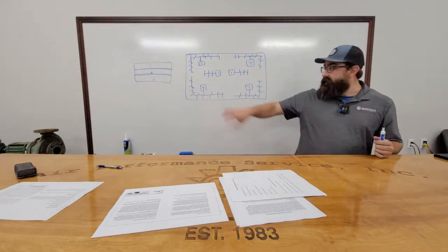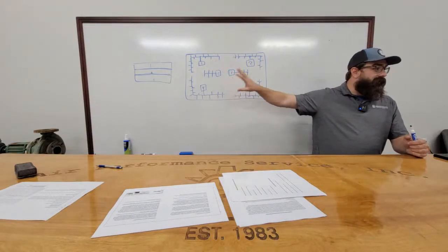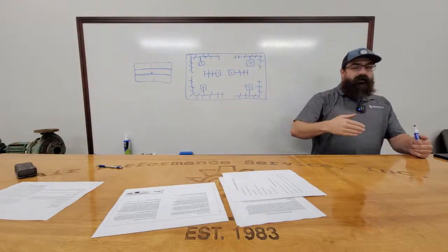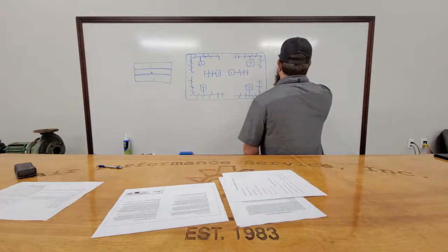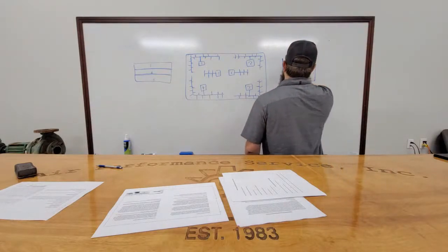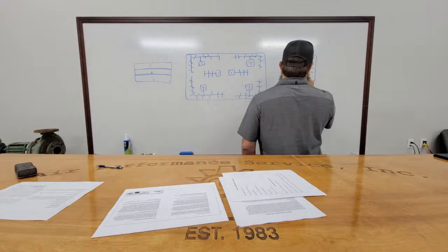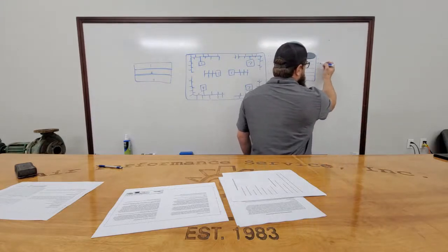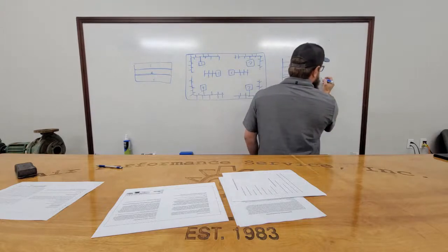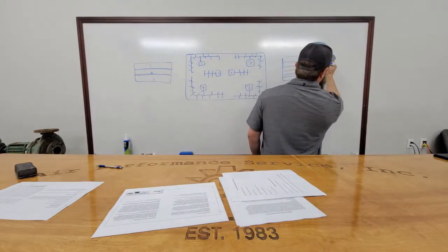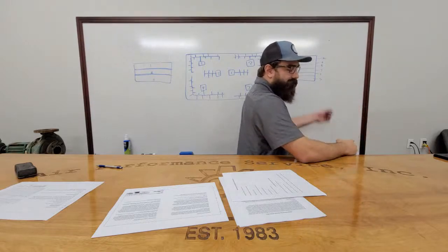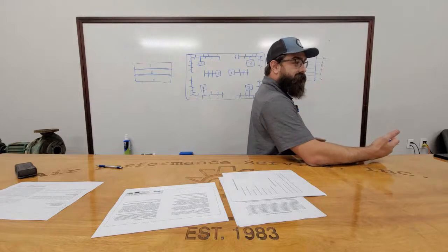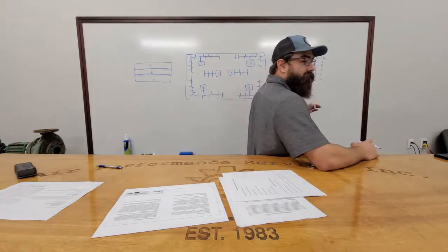Yeah, like I said, in this building that I'm referencing, they don't have to do any of that. It looks at outside air temperature, it looks at space temperature, and it determines on its own what it starts first. In a typical standard building with six floors, each floor is going to have its own schedule. He may start this one at 5, 6, 7, 8, 9, 10 a.m. The building engineer would determine which one of those comes on based on a schedule. Whereas in this building, we know we want the building running by 8 o'clock.